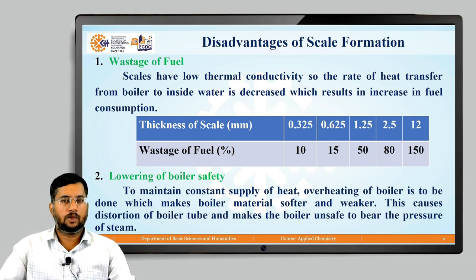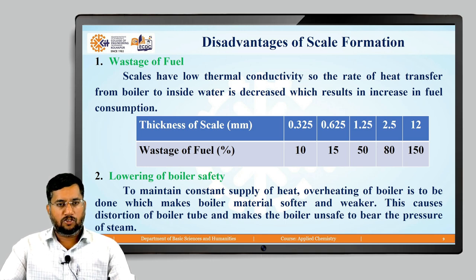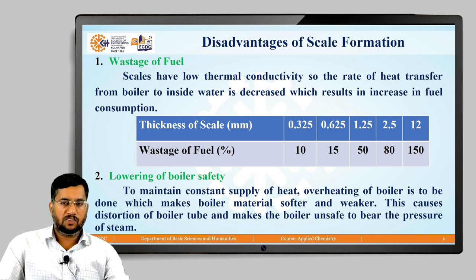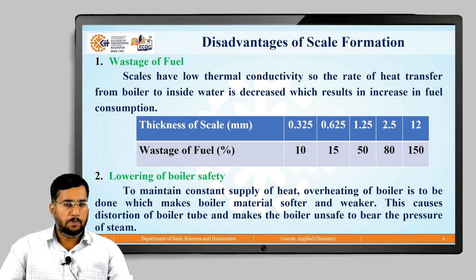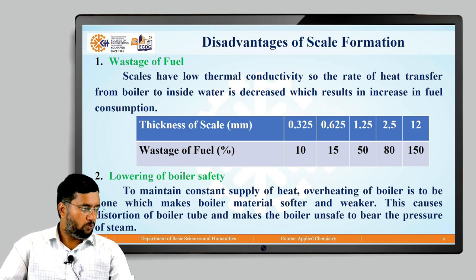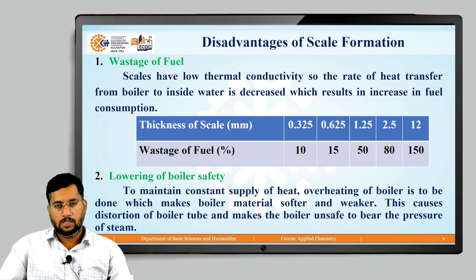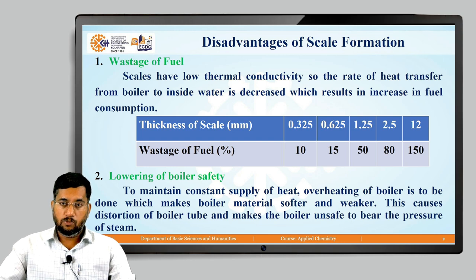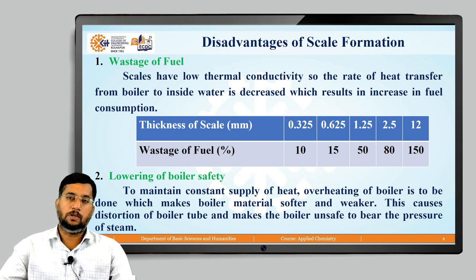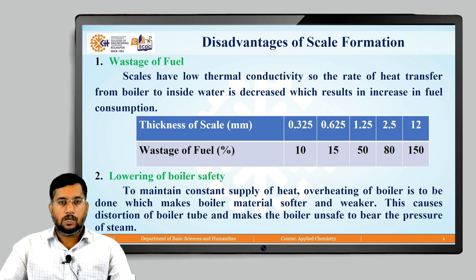A table illustrates the relationship between scale thickness and fuel wastage: a scale thickness of 0.325 mm causes 10% fuel wastage; 0.625 mm causes 15% wastage; 1.25 mm causes 50% wastage; 2.5 mm causes 80% wastage; and even 12 mm thickness results in 150% fuel wastage. This shows how severely scale decreases boiler efficiency.